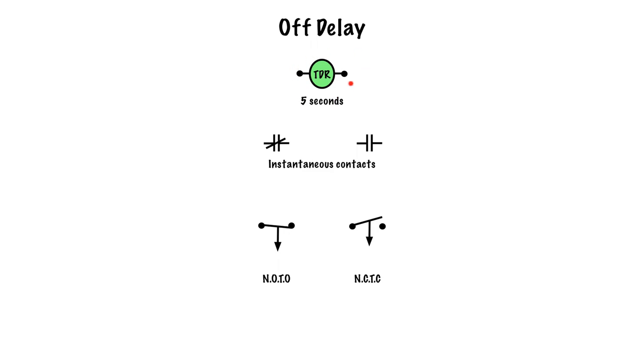Let's say TDR was running for about half an hour: this stays closed, this stays open, this stays closed, this stays open. That five-second timing has nothing to do with any of this while TDR is energized. The timing only becomes relevant when we de-energize TDR.